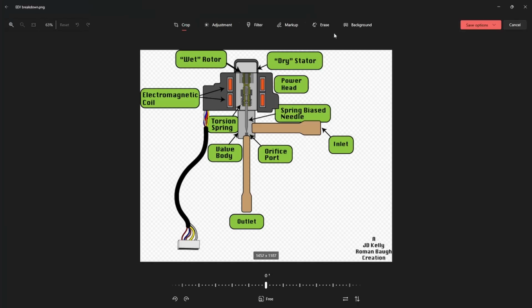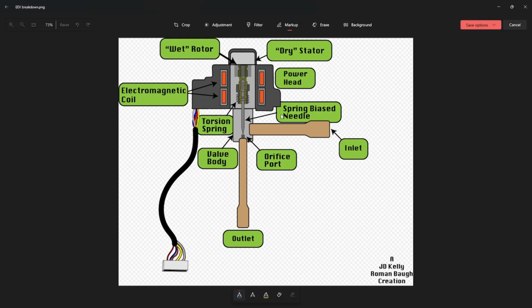So this diagram here is a view of what's inside the stepper motor. Inside your stepper motor, there's a couple of big parts to pay attention to. Your power head is what the entire assembly here is called. That's our stepper motor. So in your power head, you guys will notice that you have electromagnetic coils right here and right here. They surround the needle. The needle is inside the actual valve body, and that is what gets brazed onto the liquid line and the coil inlet. So the valve body and the stepper motor are two completely different pieces of this valve.